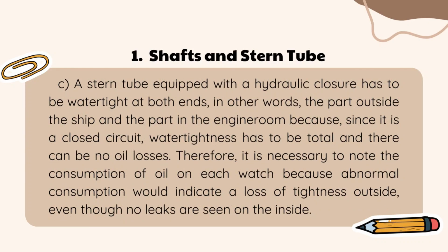C. A stern tube equipped with a hydraulic closure has to be watertight at both ends, in other words, the part outside the ship and the part in the engine room, because, since it is a closed circuit, watertightness has to be total and there can be no oil losses. Therefore, it is necessary to note the consumption of oil on each watch, because abnormal consumption would indicate a loss of tightness outside, even though no leaks are seen on the inside.